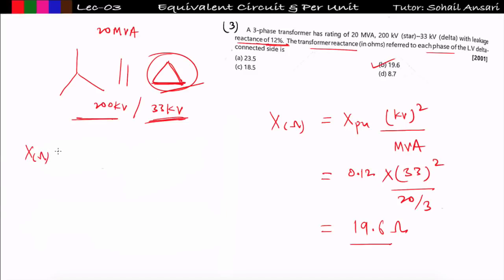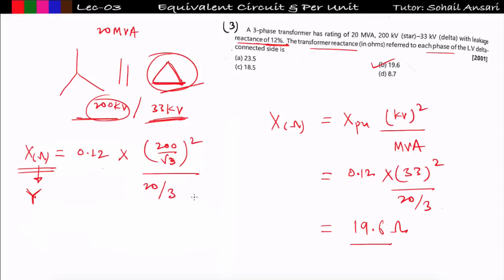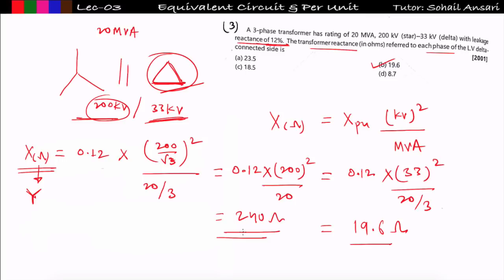If the question asked for transformer reactance referred to the high voltage (star) side: per phase voltage on star side = 200 kV / √3. X in ohm = 0.12 × (200/√3)² / (20/3) = 0.12 × 200² / 20 = 240 Ω. Although the actual reactance values on primary and secondary differ, the per unit value remains the same on both sides. That's all about this lecture.